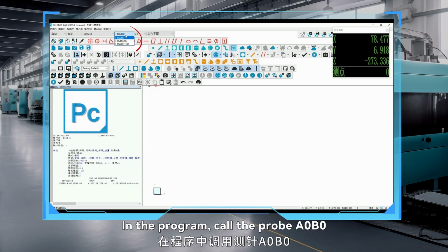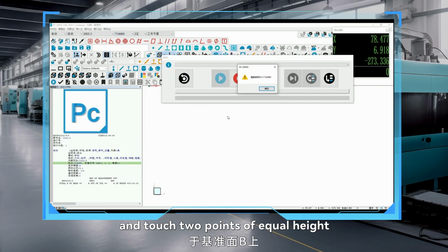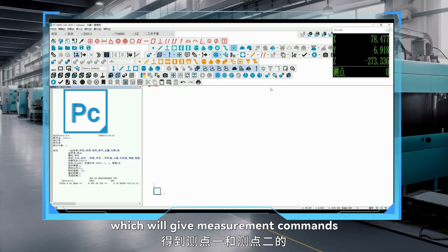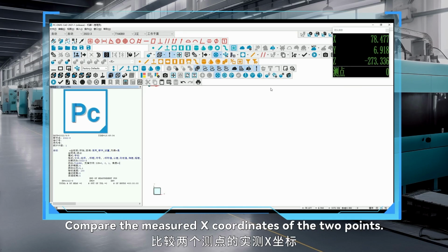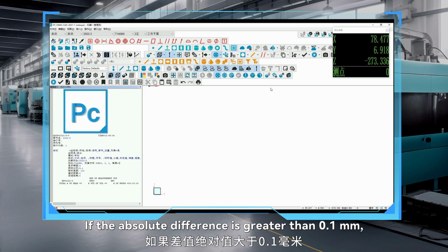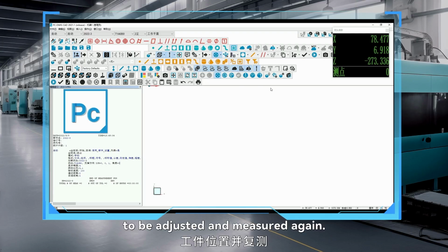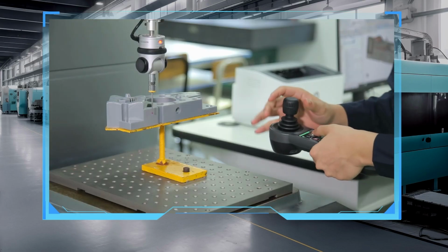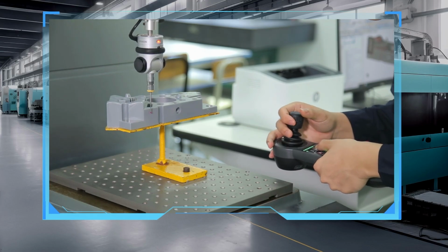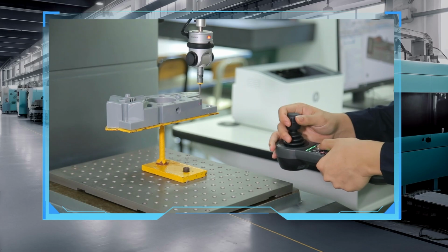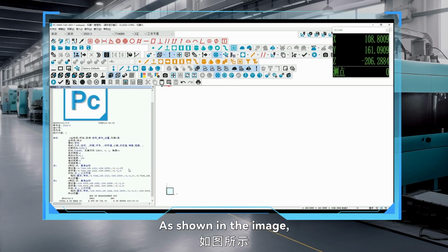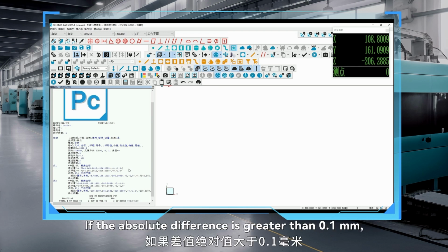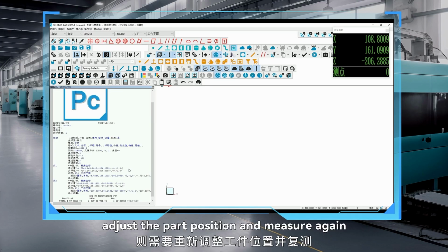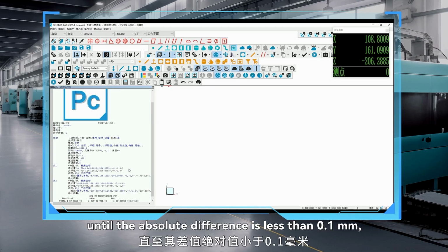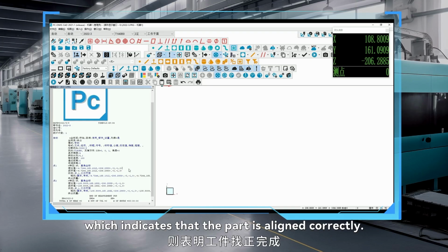Next, align the part. In the program, call the probe A0B0 and touch 2 points of equal height on reference surface B, which will give measurement commands for point 1 and point 2. Compare the measured x coordinates of the 2 points. If the absolute difference is greater than 0.1 mm, the part position needs to be adjusted and measured again. As shown in the image, compare the measured y coordinates of the 2 features. If the absolute difference is greater than 0.1 mm, adjust the part position and measure again until the absolute difference is less than 0.1 mm, which indicates that the part is aligned correctly.